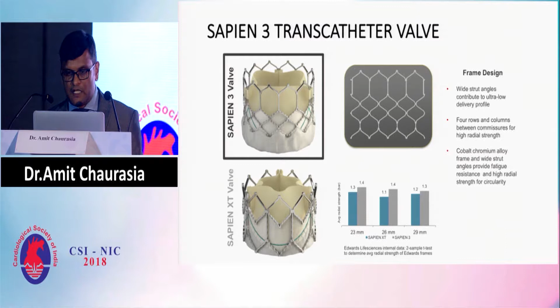Now this is a balloon expandable valve, and all balloon expandable valves we size based on the area, and depending upon the area the valve sizing is done. Now this valve, when crimped, comes in 23, 26 and 29 millimeter. Now a 20 millimeter valve is also available, and the crimped height is something like 24.5 millimeter, 27 millimeter and 31 millimeter respectively.